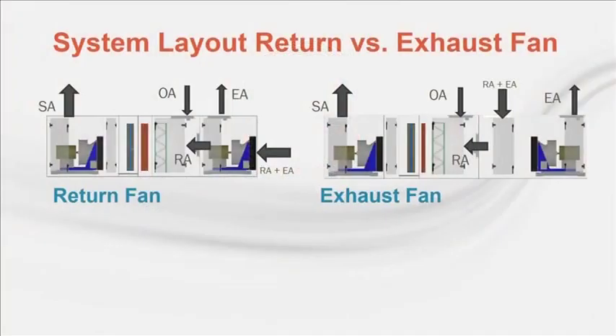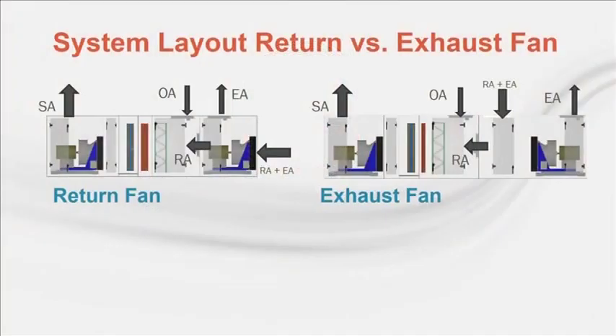Return fans are traditionally used for systems with high return duct static pressure. Not only will utilizing a return fan alleviate some of the work required by the supply fan, the system will require less work from the fans. If there is not a high return duct static pressure, the return fan may still reduce the size of the supply fan. However, overall it will require more fan power than an exhaust fan system.